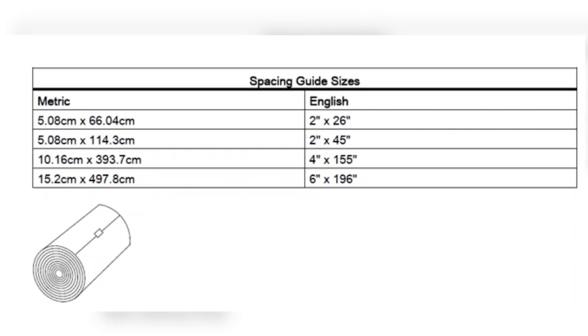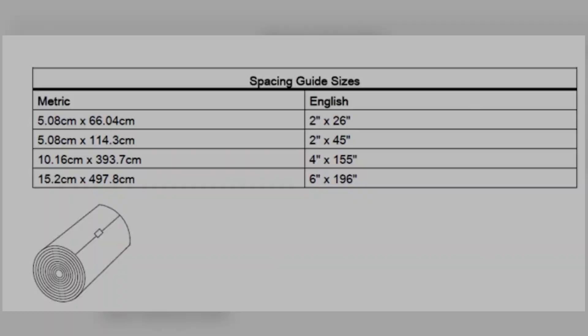Every install will come equipped with a Mylar Spacing Guide. You can use this guide to wrap around the pipe and find the opposite end of the pipe to get a true 180-degree offset between the sensor on one side and the sensor on the opposite side.